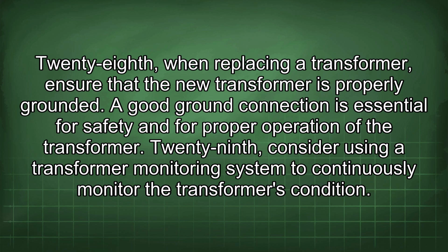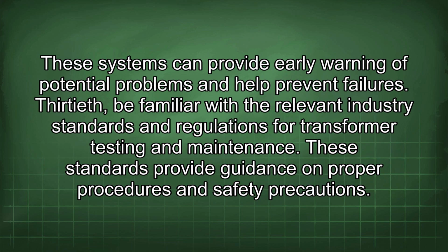28th, when replacing a transformer, ensure that the new transformer is properly grounded. A good ground connection is essential for safety and for proper operation of the transformer. 29th, consider using a transformer monitoring system to continuously monitor the transformer's condition. These systems can provide early warning of potential problems and help prevent failures.